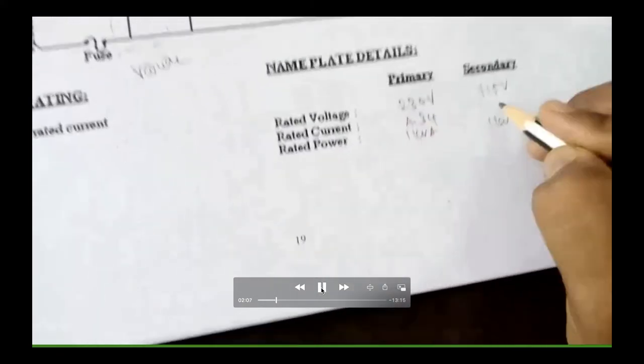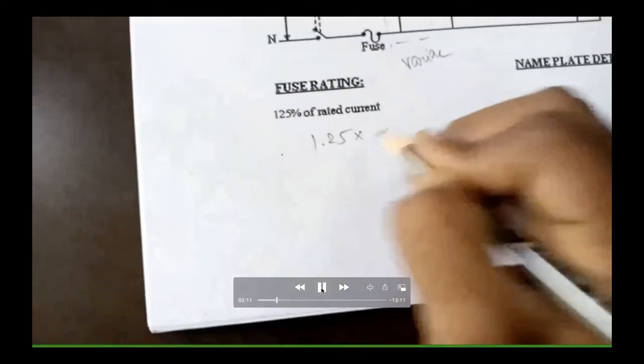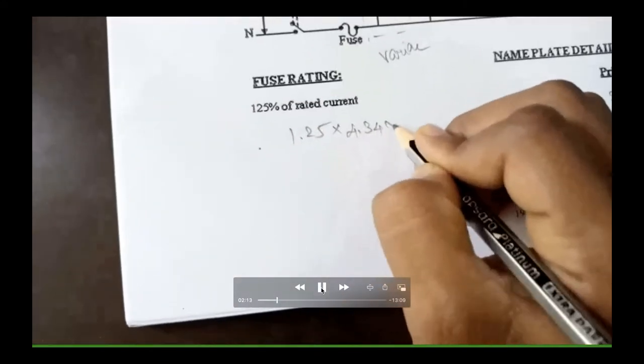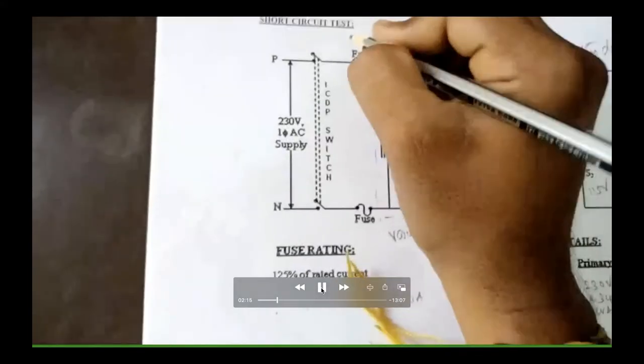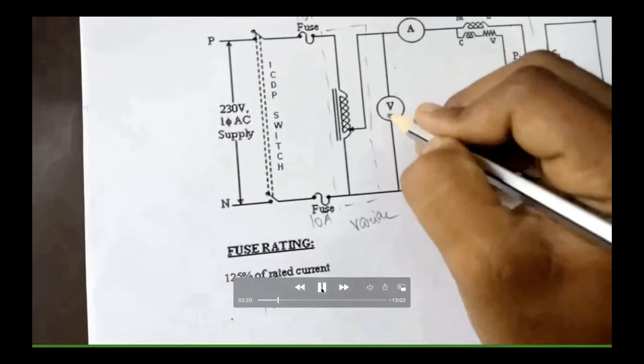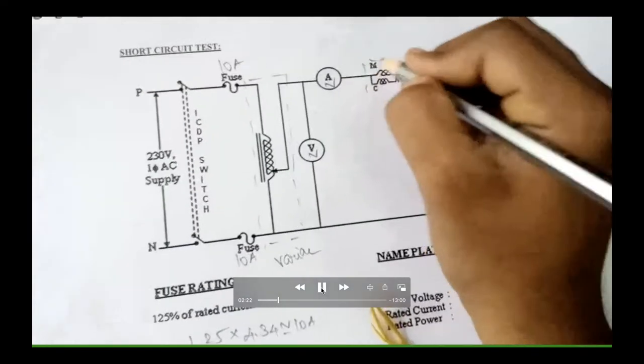So primary will be 230 volt, secondary will be 115 volt. So the current will be reversed. Primary current will be 4.34, and secondary current will be 8.6. So the fuse setting, in case of the load test, will be 125% of rated current, 1.25 into 4.3, which is almost 10 amps. And the primary ammeter and voltmeter are on this side.